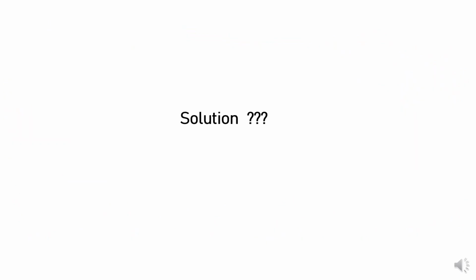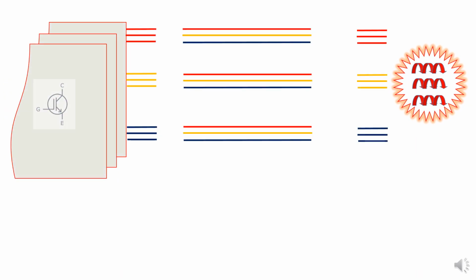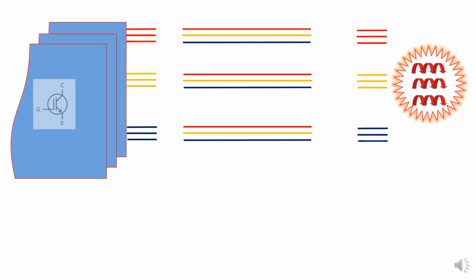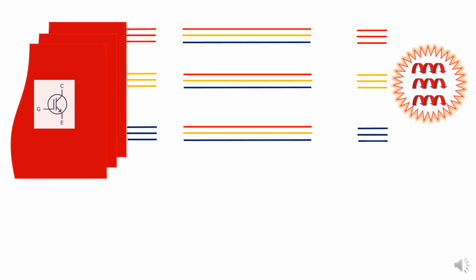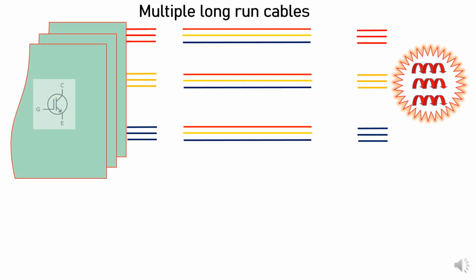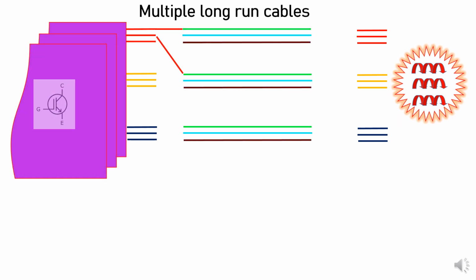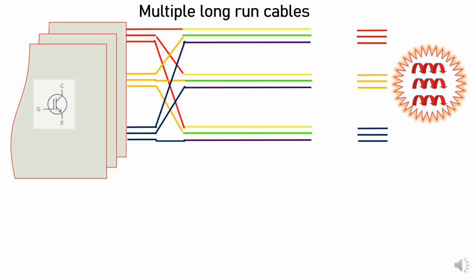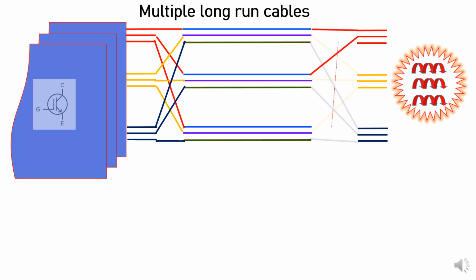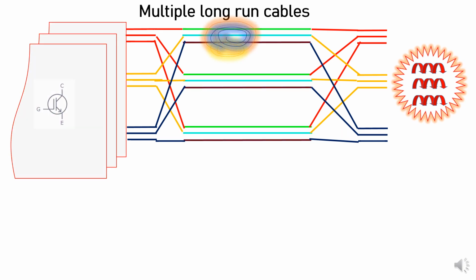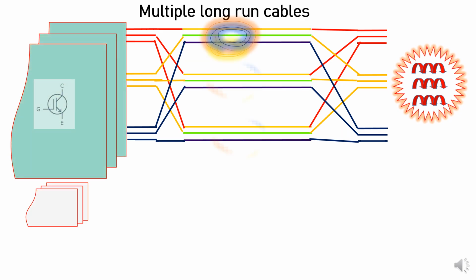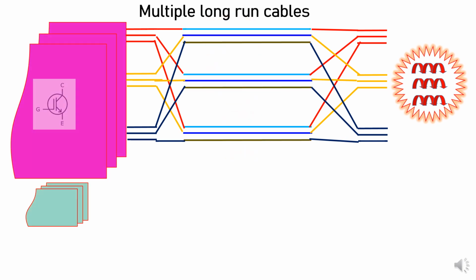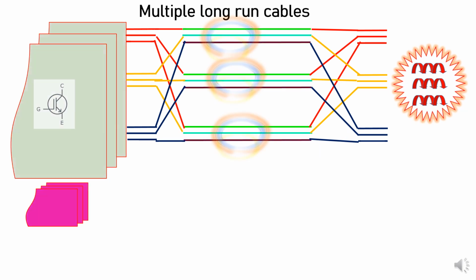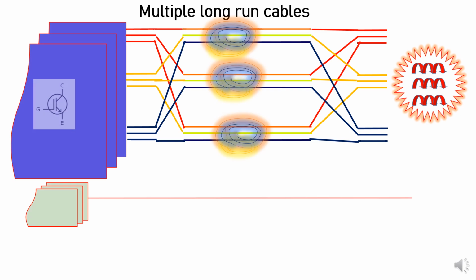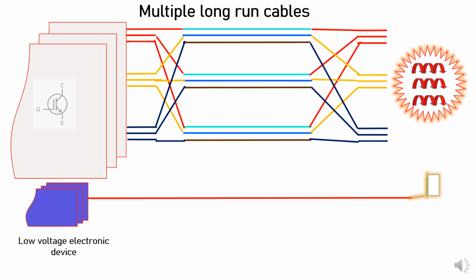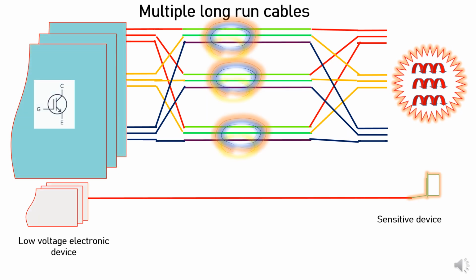So what are the solutions? How can we avoid this with our physical cable laying practices? Beautifully, you can see here, if you are running with multiple long run cables, the first one is this type of arrangement. This is called a transposition connection of the cable at the VSD end, and the same cable termination needs to be taken care of so that the field generated by each and every cable run will be nullified by each other, and at last it will cancel each other in a long run, and the side-by equipment will not see any type of abnormality.